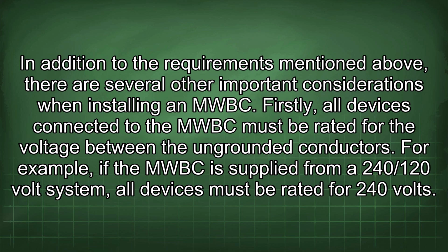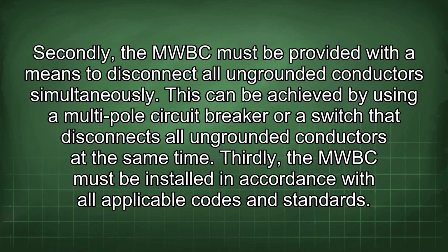Firstly, all devices connected to the MWBC must be rated for the voltage between the ungrounded conductors. For example, if the MWBC is supplied from a 240/120 volt system, all devices must be rated for 240 volts. Secondly, the MWBC must be provided with a means to disconnect all ungrounded conductors simultaneously.